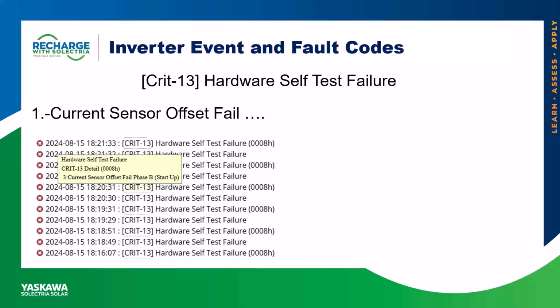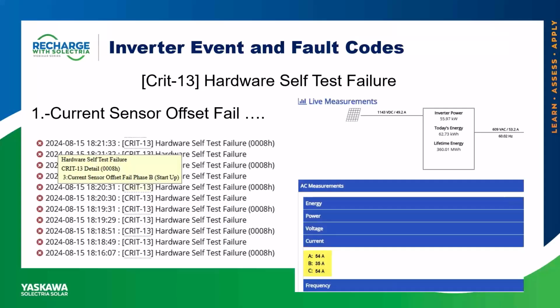Now, if your inverter is producing power, it's running perfectly fine, but you see these fault codes in the past, a quick troubleshooting step you can do is go to the live measurements, under AC measurements and current. You will notice that there's going to be a current imbalance. As you can see in the picture, phase A is showing 54 amps, phase C is showing 54 amps, but phase B is showing 35. So right off the bat, you know that phase B has a CT problem and it will need to be replaced.